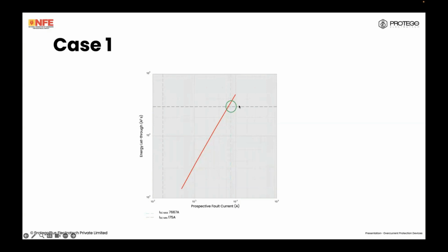I was at a site in Hyderabad, and it was a building, and the building's demand was about 100 amperes. They put a 35 square millimeter cable, which is more than enough for what the cable can handle. However, the short circuit protection device was a 630 ampere MCCB set to times 10. This is a situation where the cables are big, but the breakers are oversized so much that the fault current is not going to be effectively current limited by the breaker, and you're going to have damage to the cable.